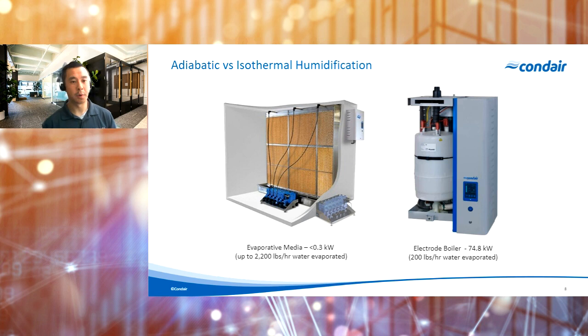So again, if we just compare those two processes, an adiabatic process is an increase in humidity with a temperature decrease. An isothermal process is an increase in humidity at constant temperature. Now, if we compare the energy requirements between those two processes, depending on the type of system, for example, here, if we're evaporating 200 pounds or 24 gallons of water, a typical electrode steam humidifier would consume about 75 kilowatts of electricity.